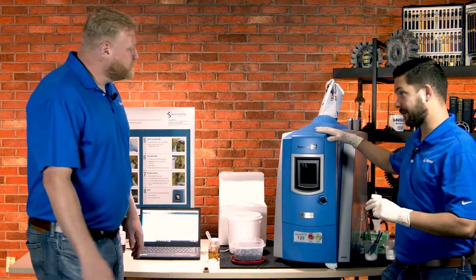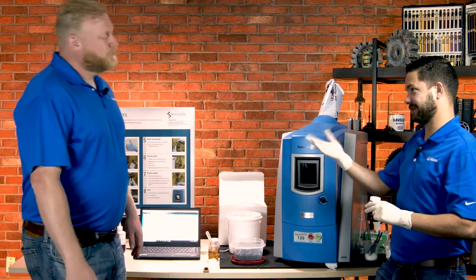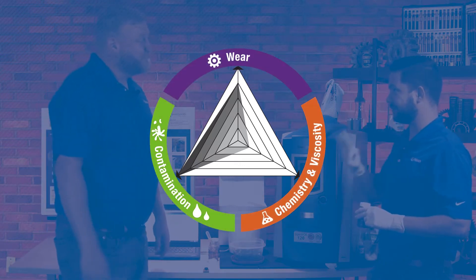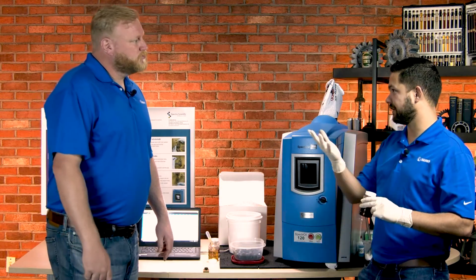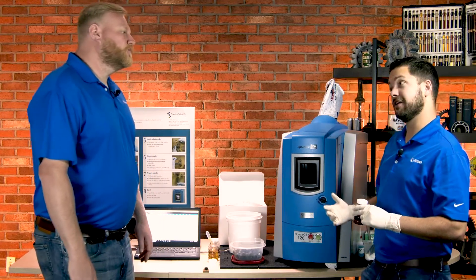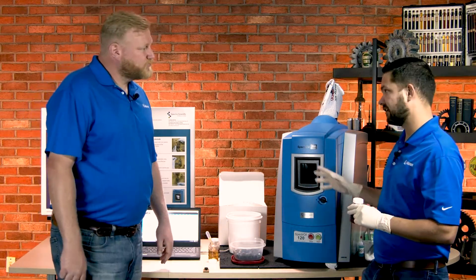This is the Spectroil 120 by Ametek Spectro Scientific — an elemental spectrometer. When we think about oil analysis, we think about the iron triangle: lubricant health or condition, contaminants getting into the lubricant, and wear debris generation. These three categories appear across every oil analysis report — they're the backbone. We want to watch trends of wear debris increasing or contaminants on the rise, and you can also trend the downward trend of oil additives.